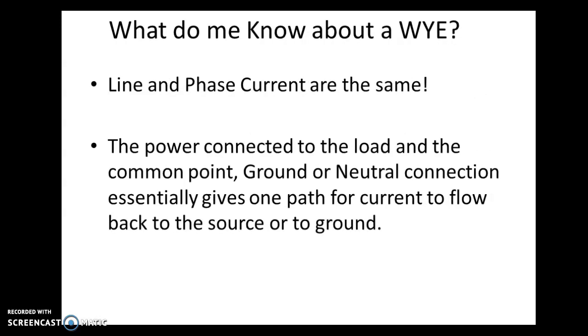Alright, continuing on with the Y connection and what we should know about it to this point. Line and phase current are the same. So in other words, if you put your clamp-on ammeter on one of the lines for a Y connection, it should be exactly the same as the phase. This is because the load is typically connected in series back to ground, or the neutral point, or the common point, and this is giving us essentially one path for current to flow.